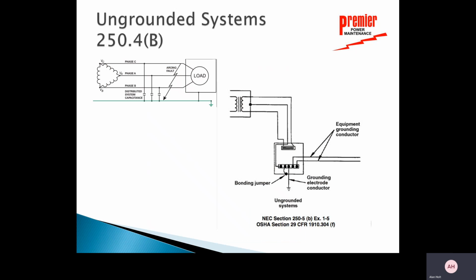So let's talk briefly about ungrounded systems. There are ungrounded systems, three-phase, three-wire, 240 volt, three-phase, three-wire, 480 volt delta-based systems used basically for motor type loads, okay? So that would be the basic reason for those things. And so I have the three phases here connected delta. I've got distributed capacitance. Those are not capacitors. That's just distributed capacitance on the cable. But you see, the case of the motor is grounded, but there are no grounds on any of the conductors here. So that's completely floating.